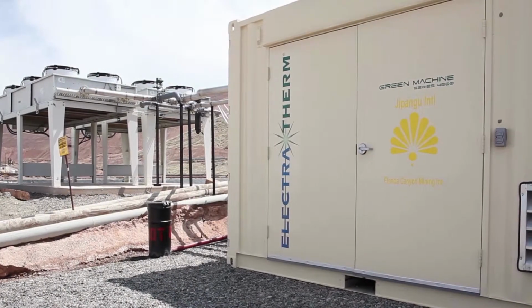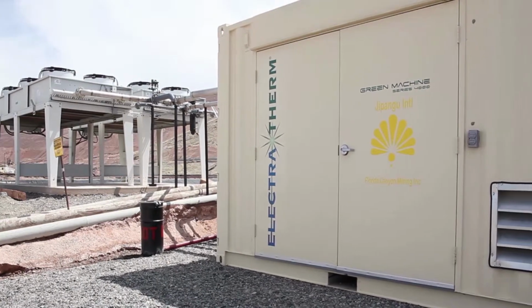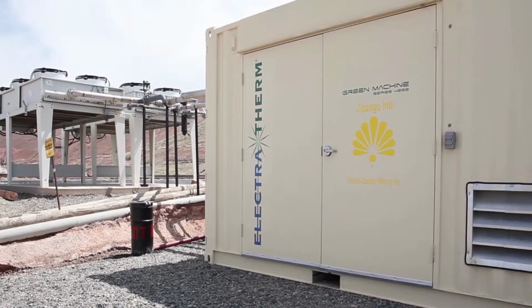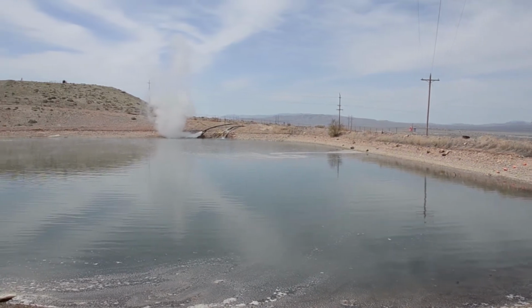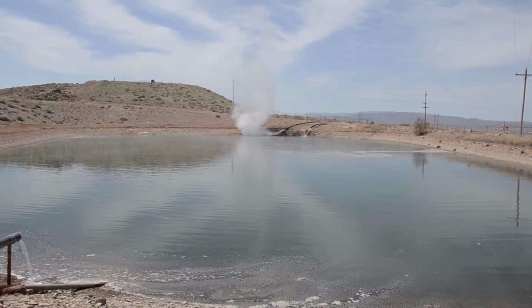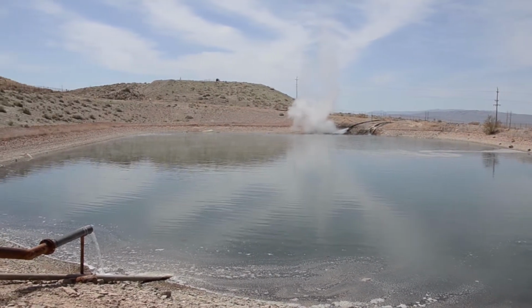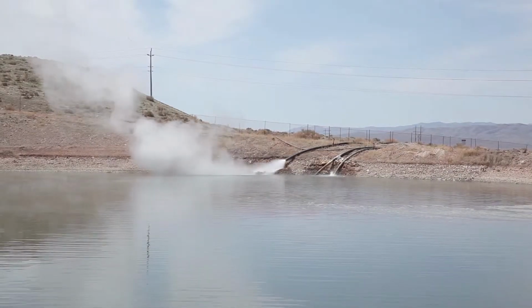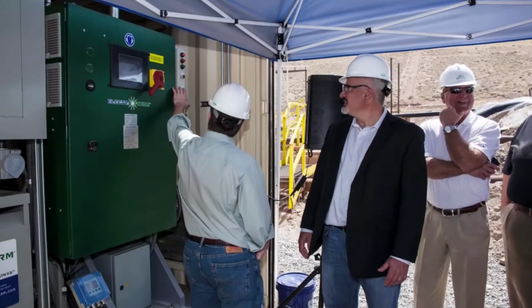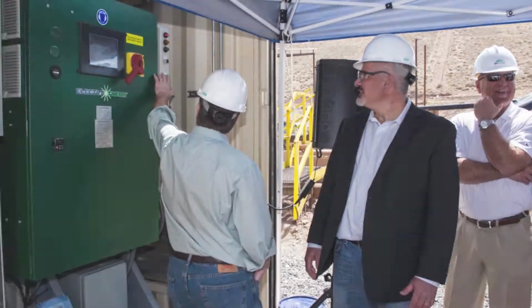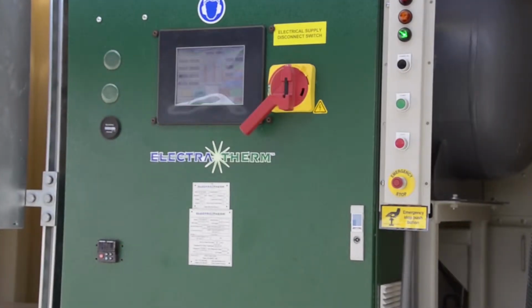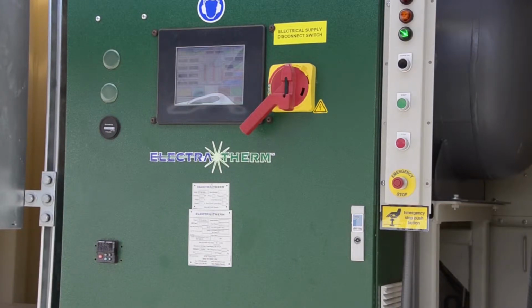The way this works is we take heat, in this case from geothermal water, into a heat exchanger where we boil our working fluid. From there, the vapor goes through a twin screw expander connected by a belt to a generator, which puts electricity on the grid. The vapor then travels to a condenser where it's returned to a liquid, and is pumped back to the heat exchanger to complete the cycle. It's a completely closed cycle that generates no outputs other than fuel-free, emission-free electricity from low-grade heat.